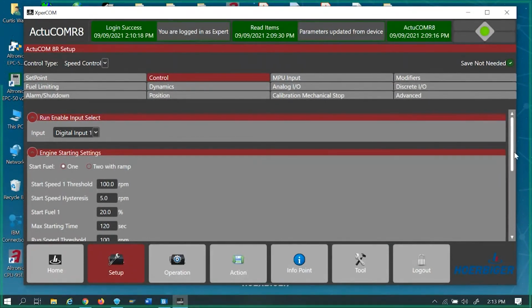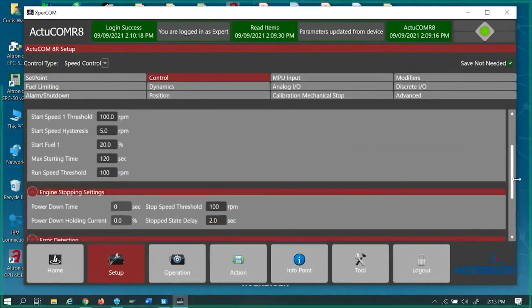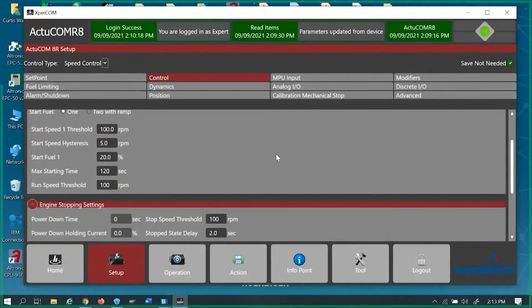Our engine starting settings. You have start thresholds. It says don't do nothing until I get to a certain threshold. It won't go to run until it hits it. It'll stay in the start until it hits whatever you put in here, then it'll go into a run. So a start threshold, if I say 100 RPMs, basically says I'm trying to start.